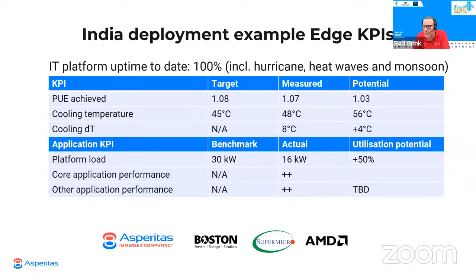The design was for 1.08, actual PUE measured was 1.07, and further reduction is anticipated to 1.03. That relates to a dry cooler configuration. The cooling temperature was designed for tolerance at 45 degrees Celsius, but the platform has been evaluated and supported for operating temperatures up to 48 degrees Celsius, and we've identified further potential to increase that temperature tolerance to 56 degrees Celsius. This means this platform can run anywhere in India without compression or adiabatic cooling systems.